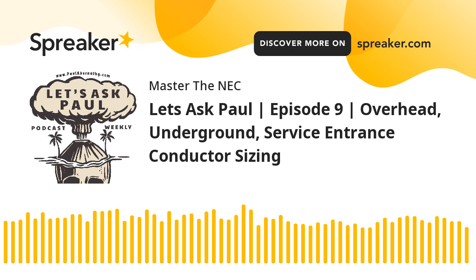Now, we have some exceptions, and I'll explain those which are more relevant to our situation, but the general rule is that whatever my ampacity of my conductor is, my overcurrent protection is what? Equal to or not greater. So it's not higher than the ampacity of the conductor. General rule, you with me? That's the general rule. So we're protecting those conductors. In our case, the only thing we're really protecting these service conductors for is overload, because we really can't give any short circuit or ground fault protection, because why? It's on the supply side. It's not on the load side.